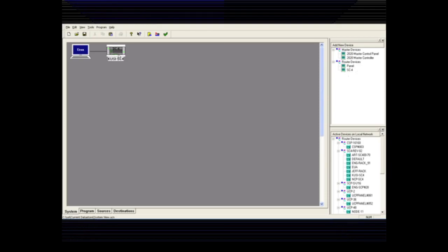Until the red box goes away, you'll never be able to reprogram whatever you do design inside of this SC4 icon. So keep that in mind when you're building this. Now, make the name what you want it to be right now, because it's the best time to do this. Something that you don't think you'll ever need to change in the future. Now, the next release of our Yukon software, you'll be able to rename these directly here in the software. But in this application, version 3.5.7 and older, you will need to do this in the fashion that I've just shown you.